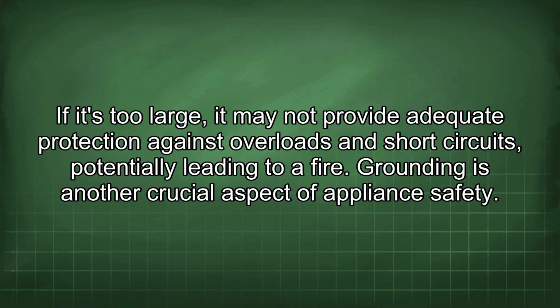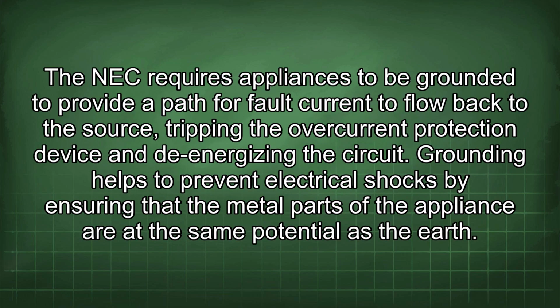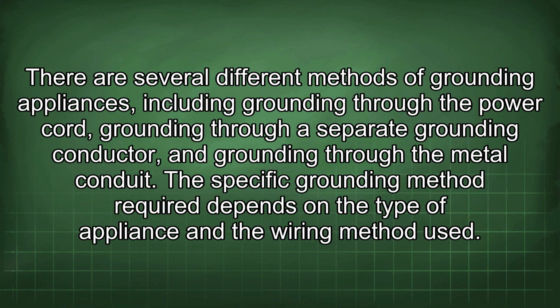Grounding is another crucial aspect of appliance safety. The NEC requires appliances to be grounded to provide a path for fault current to flow back to the source, tripping the overcurrent protection device and de-energizing the circuit. Grounding helps to prevent electrical shocks by ensuring that the metal parts of the appliance are at the same potential as the earth. There are several different methods of grounding appliances, including grounding through the power cord, grounding through a separate grounding conductor, and grounding through the metal conduit. The specific grounding method required depends on the type of appliance and the wiring method used.